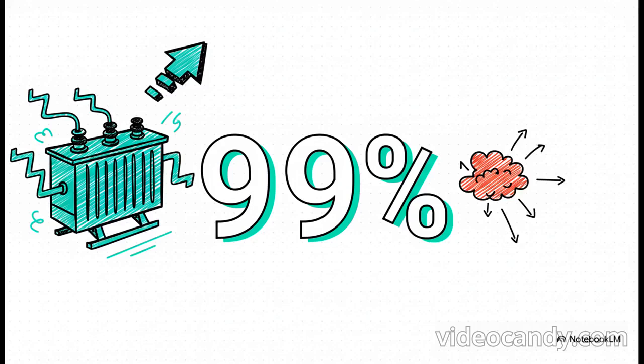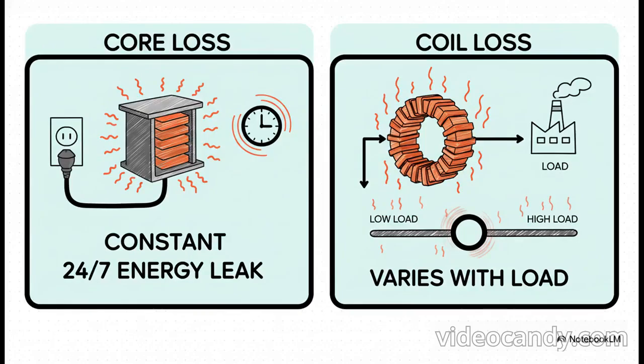But still, where does that little missing 1% go? Well, the losses basically fall into two buckets. The first is called core loss—this is just the energy it takes to keep magnetizing the core over and over. It's happening 24/7 as long as the transformer is turned on. The second is coil loss, or sometimes called load loss. This is basically just heat from the normal resistance in the copper wires. And this one changes—the more power you're using, the more heat you lose.